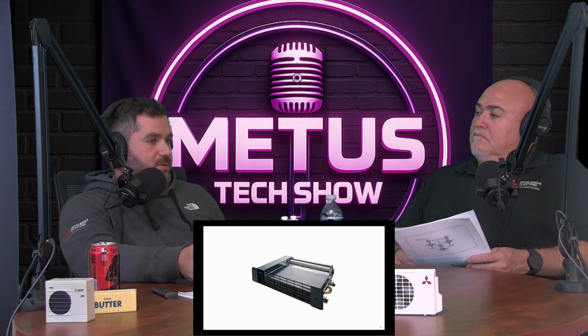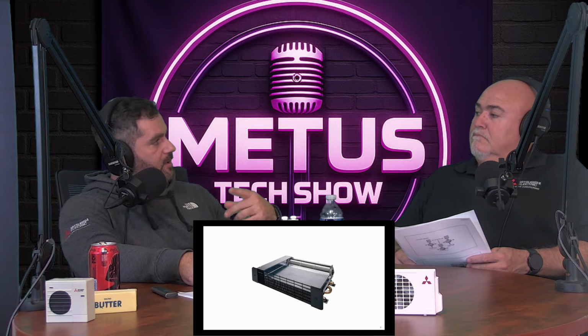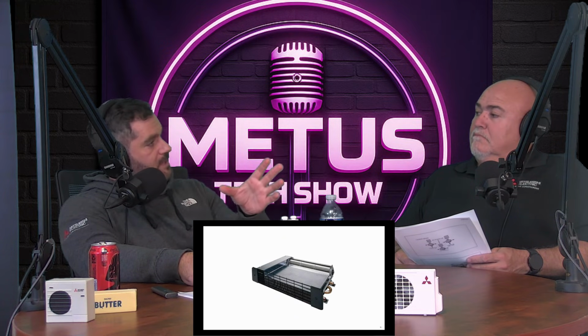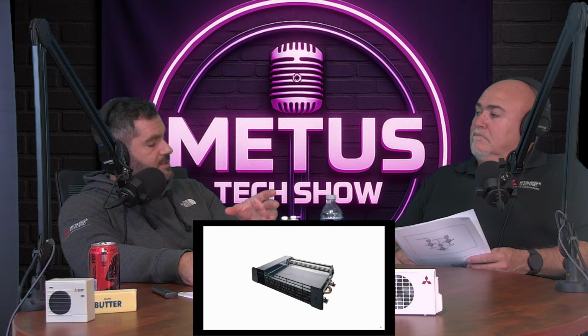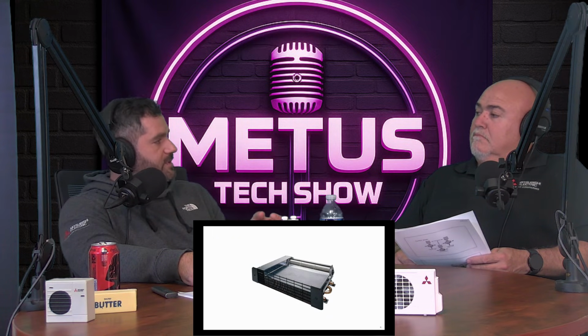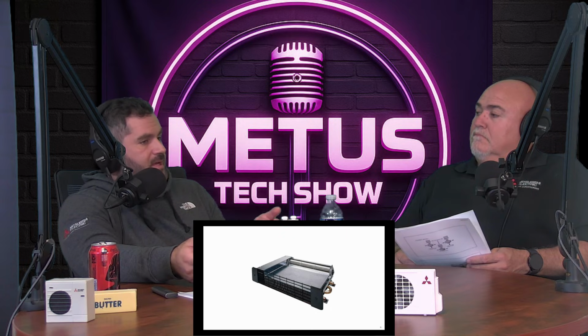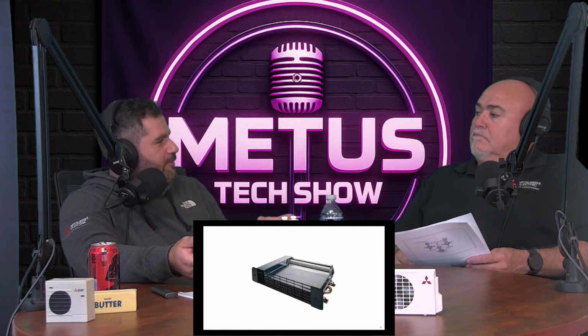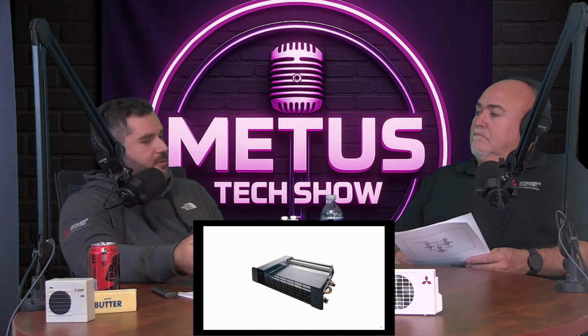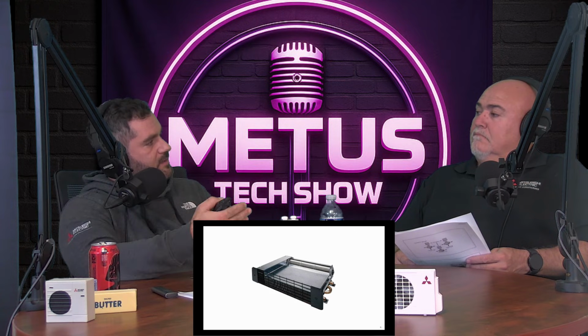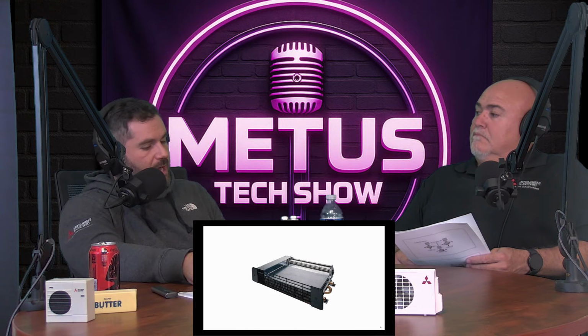And basically the way these work is it's a hydronic coil in there, and there's a blower. But that blower doesn't kick on right away. There's actually a temperature clamp on the piping, and when it reaches a certain temperature, which you can usually set yourself, we always used to do like 140-ish degrees. Once the pipe was about 140, then our fan would kick on and start delivering the air over that hydronic coil and then out into the space.